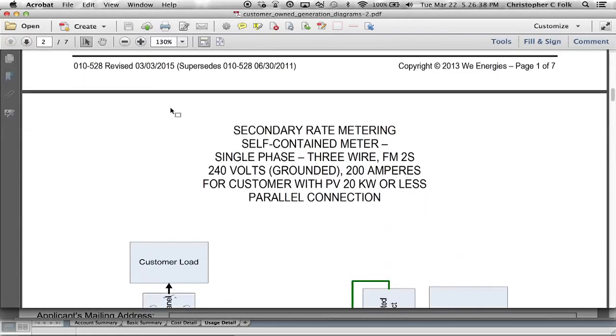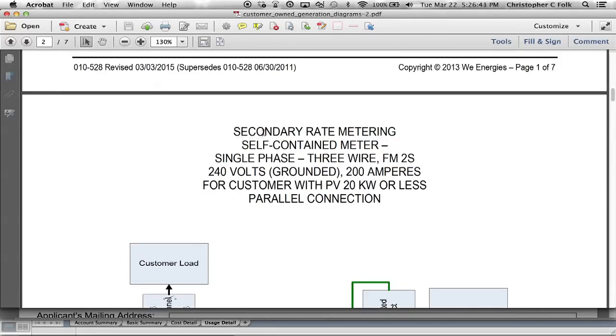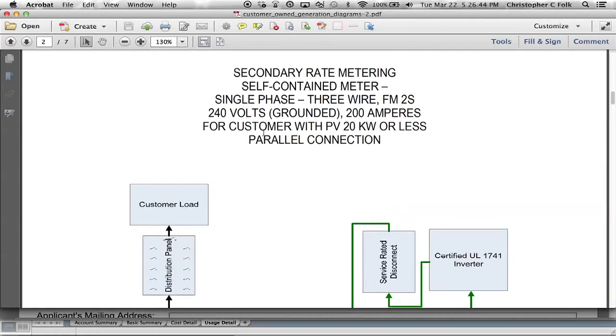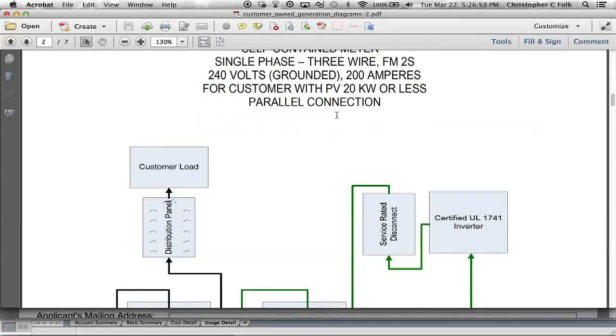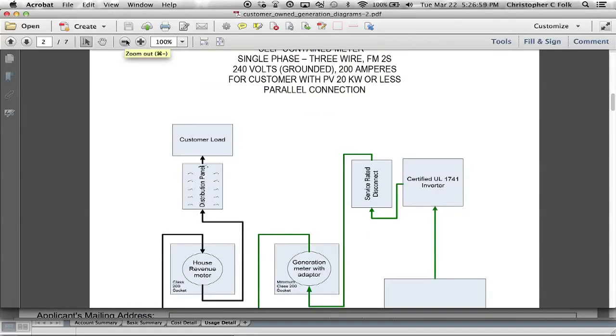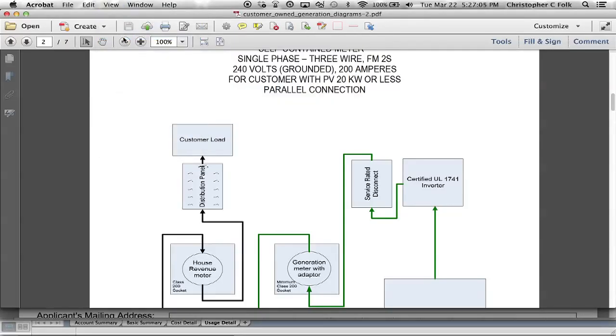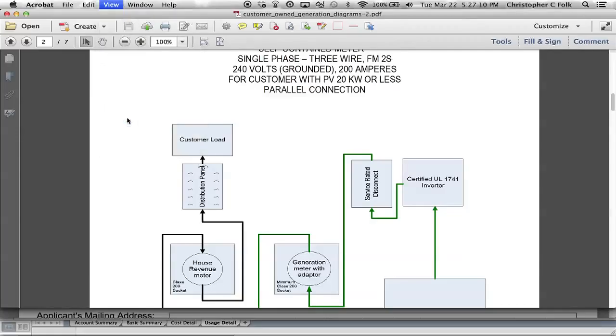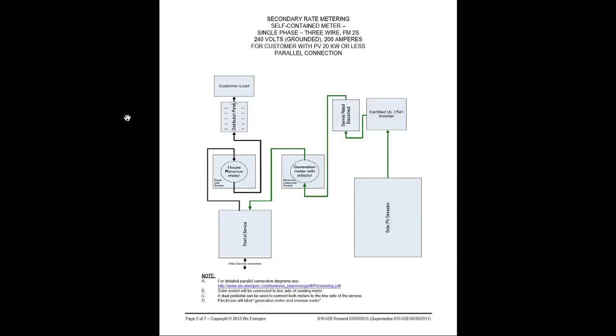The first drawing says self-contained or secondary rate metering, self-contained meter, single phase, 3-wire, 240 volts grounded, 200 amp service for a PV generated 20 kilowatts or less. Let me zoom this smaller so we can see the whole thing on the page. Maybe I can do this - window view, page display, view, full screen mode, we'll try that one. I hope I don't shoot myself in the foot here.